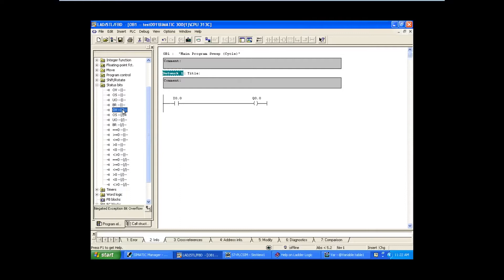So let's see how to use exception bit overflow. If we are using an integer block, there is some limit for the integer block - up to some value only you can process, and that value is minus 32768 to plus 32767.